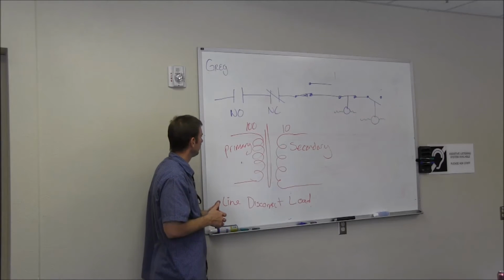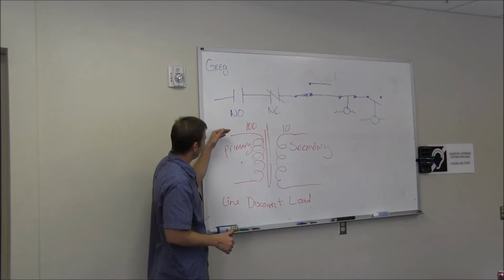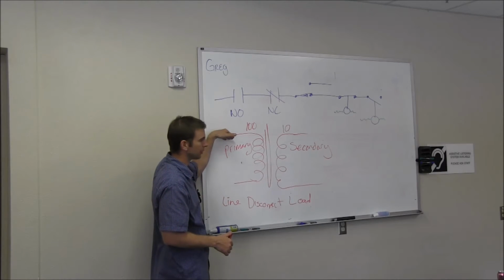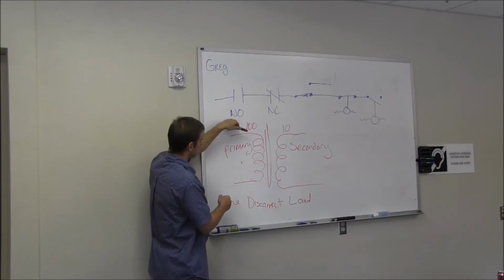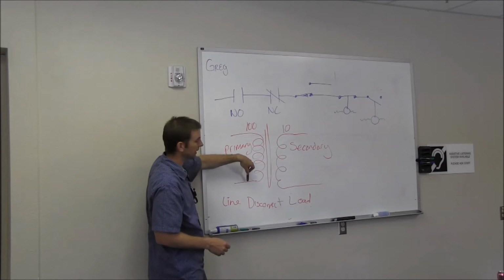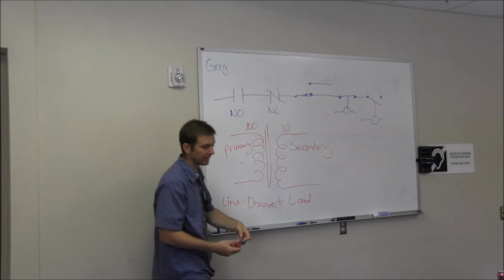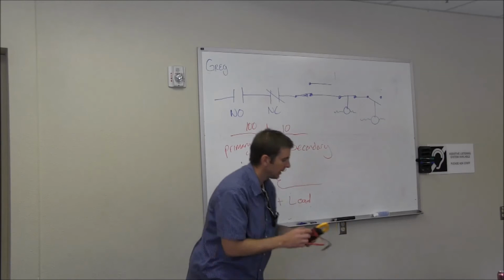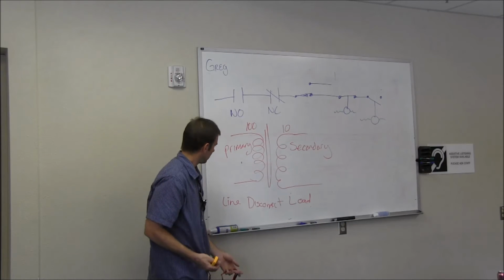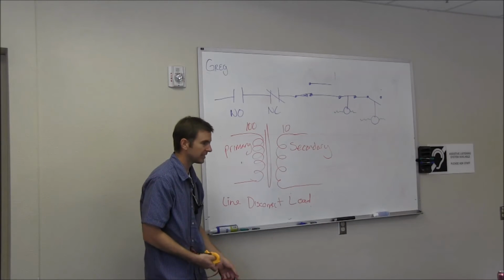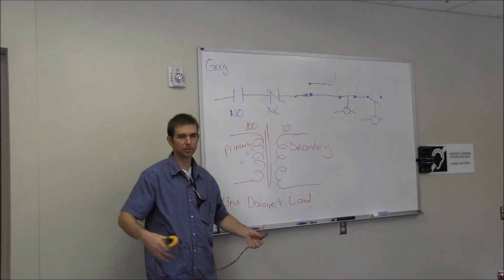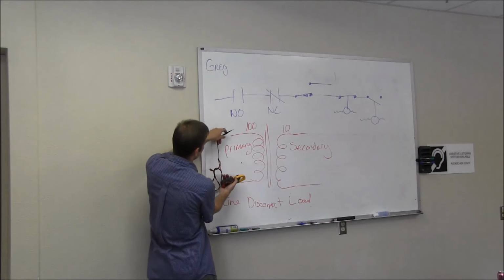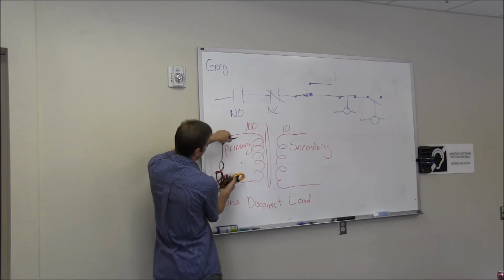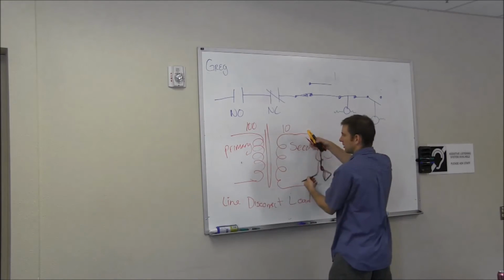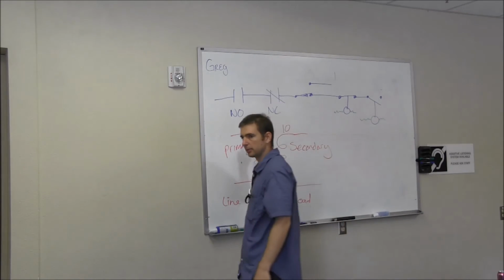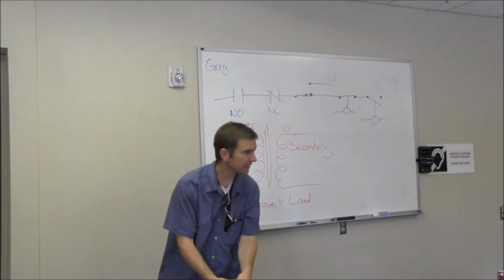Alright, so if we connect to a transformer, is this wire directly connected to this wire? Yes, if I take a continuity tester and check, yes. Well, it should be. What if I have a transformer just sitting in this room with no wires connected at all? If I test from here to here, am I going to have continuity? Yes. What about from here to here? Yes, because it's directly connected. We can see there's no break in that coil.